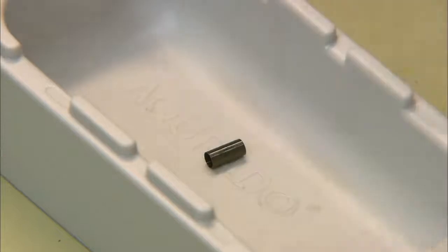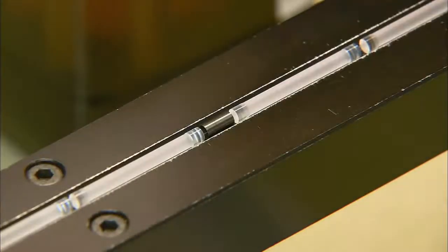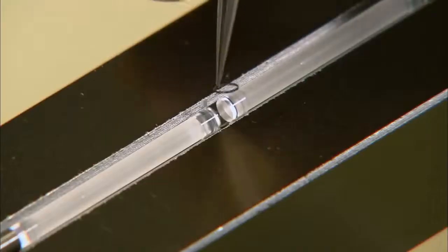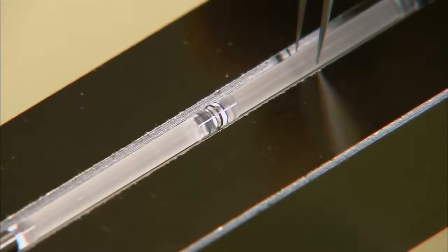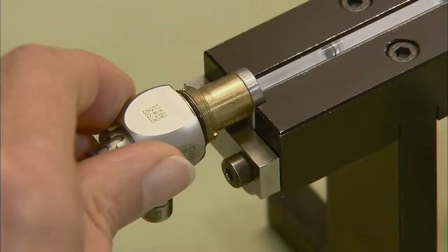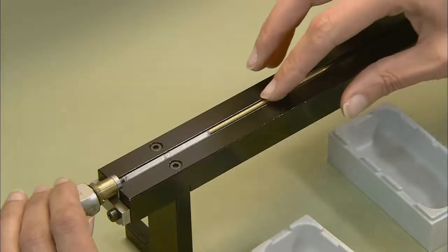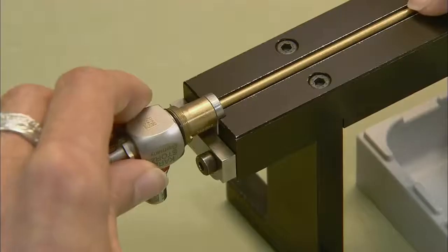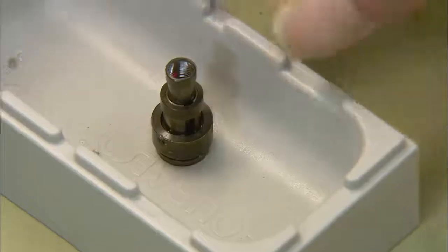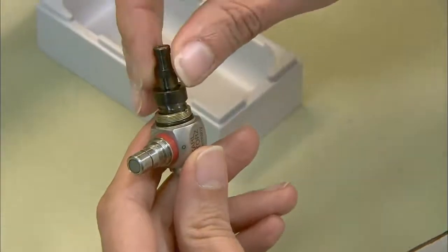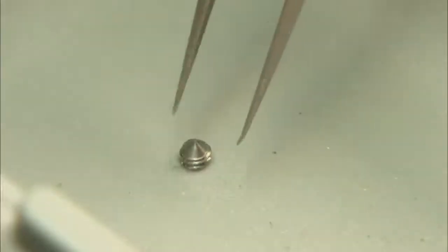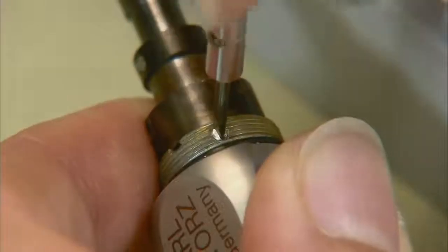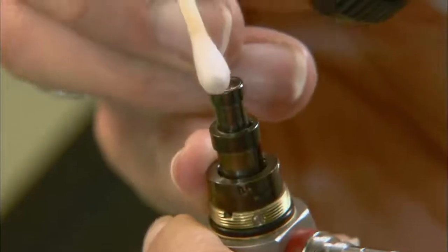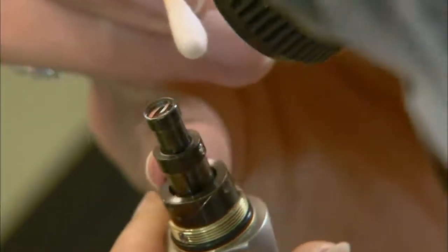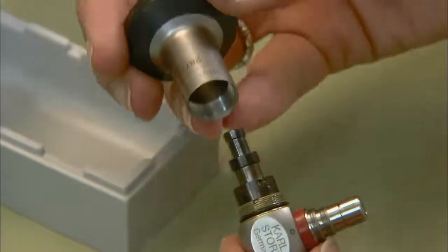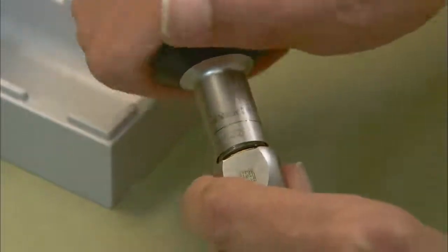Once cleaned with a chemical solution, they're aligned in a fixture, separated by brass spacers of various lengths. An endoscope may contain 5 to 7 lenses, depending on its length, and the spacers create specific distances between them. Once the image transmission system has been assembled, it can be slid into the inner tube of the endoscope. An ocular cap is then screwed on to hold everything in place. The cap's glass top is cleaned before an eyepiece is attached. This gives the surgeon the option of looking directly into the endoscope or looking at a video monitor, which receives the image via a small camera attached to the eyepiece.